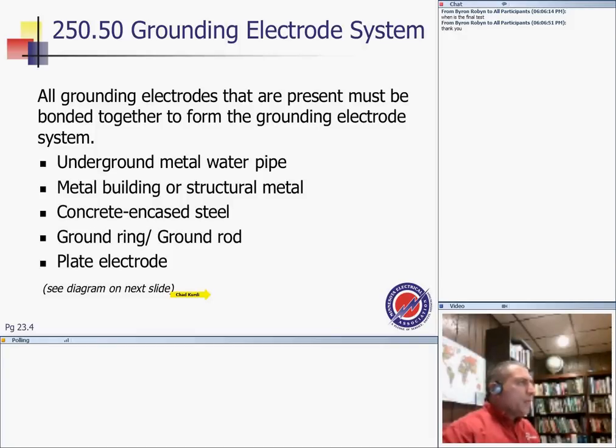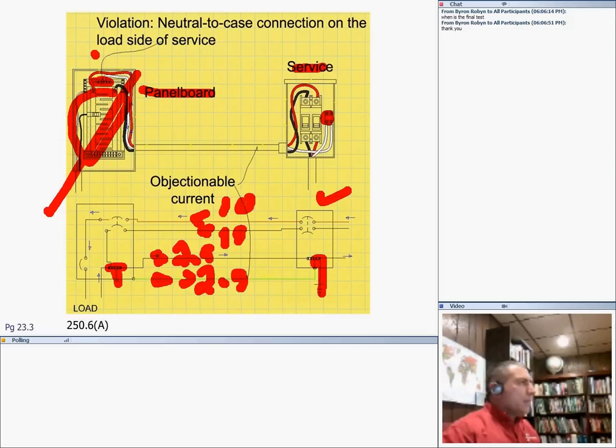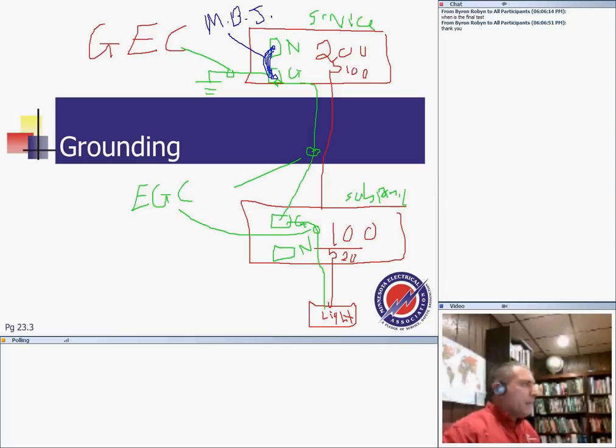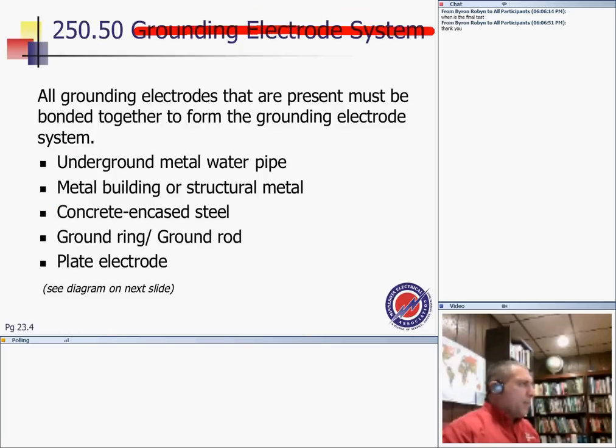Okay. So before we go ahead, guys, I want to remind you that now we talk about the grounding electrode system, and this is exactly what we meant to write in here. So we are going to talk about this particular baby in particular, right in here. That conductor going to Mother Earth. This is in particular what we're talking about: the grounding electrode conductor. That's not the main bonding jumper, just to see where we are in perspective. Okay, grounding electrode systems.